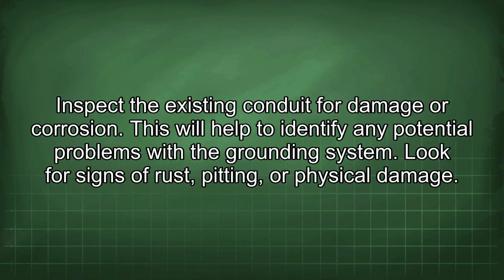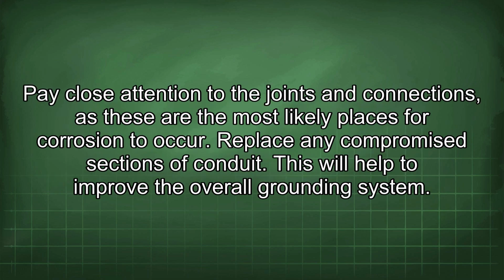Inspect the existing conduit for damage or corrosion. This will help to identify any potential problems with the grounding system. Look for signs of rust, pitting, or physical damage. Pay close attention to the joints and connections, as these are the most likely places for corrosion to occur. Replace any compromised sections of conduit. This will help to improve the overall grounding system.